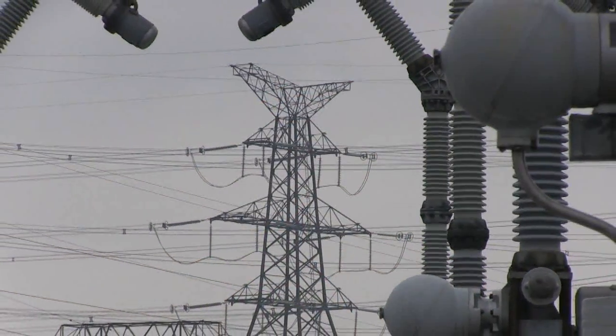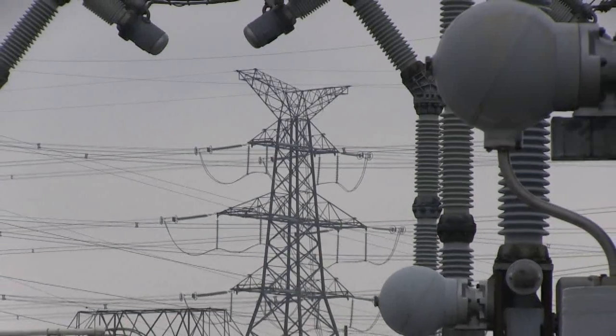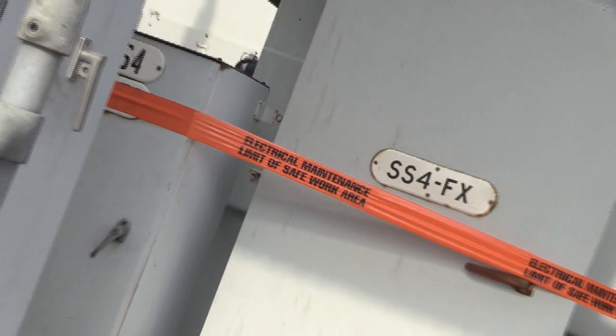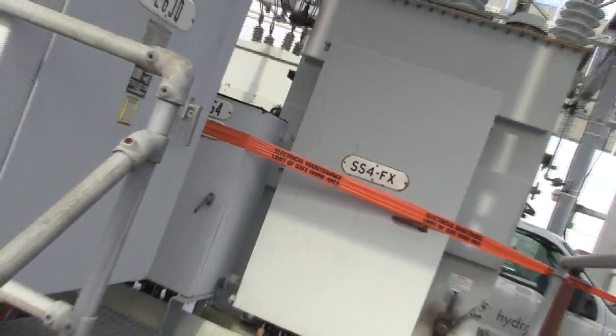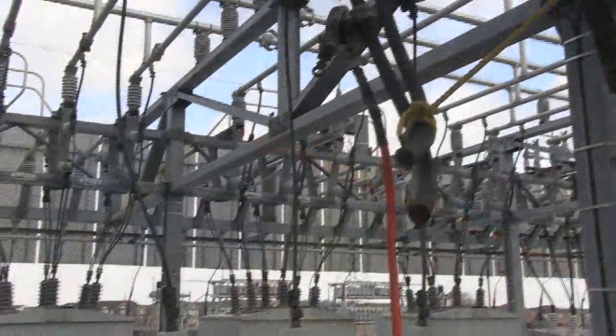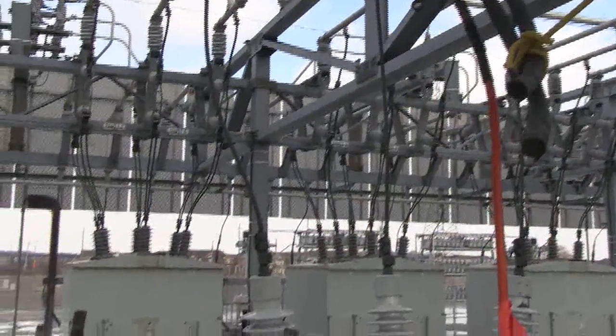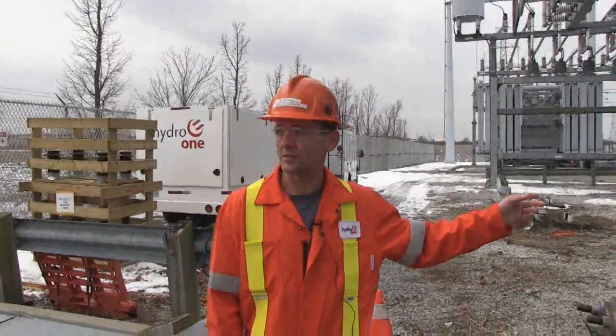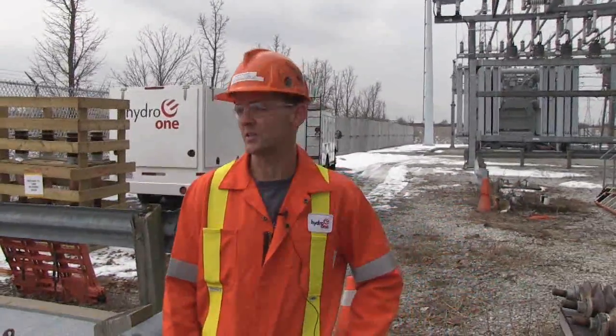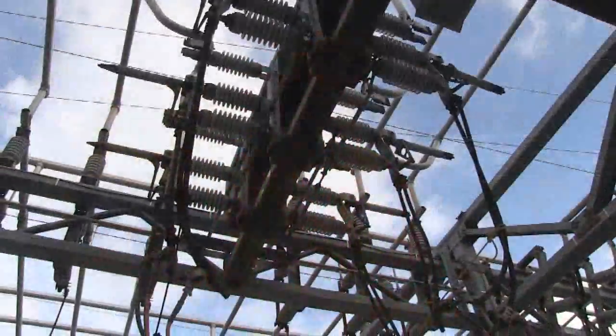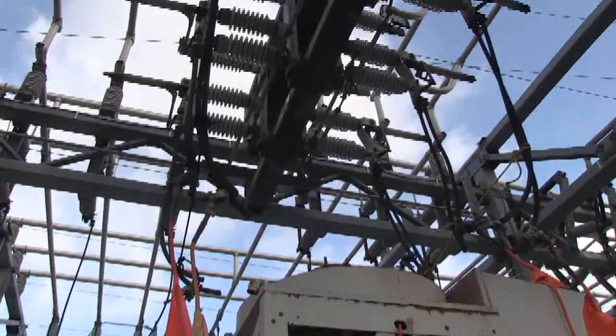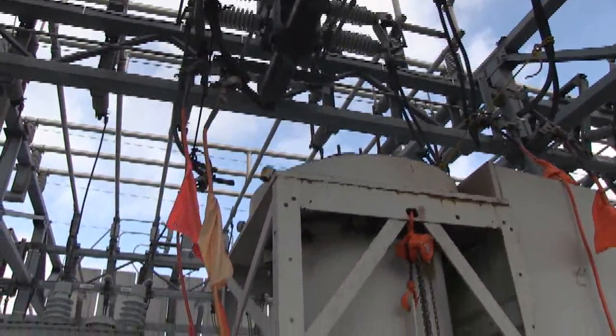You can't run a company on breakdown maintenance, you got to do it on preventative maintenance. And we have a really good program on all our switchgear and transformers to perform routine maintenance. It increases the life of your equipment. What we do is we take breaker oil analysis samples of these breakers, and if the dielectric medium of the oil starts to break down, we change the oil. So it's just like changing the oil in your car, it's ready to go again.